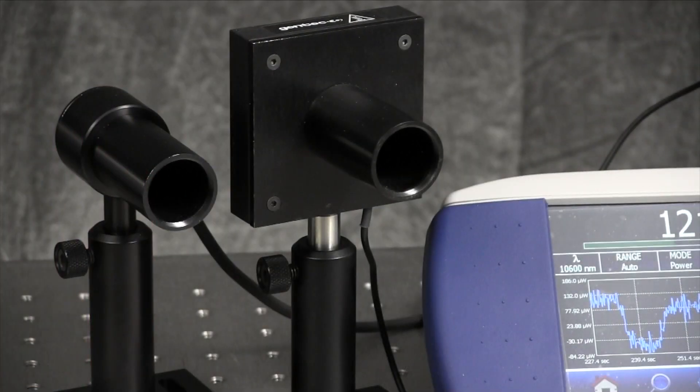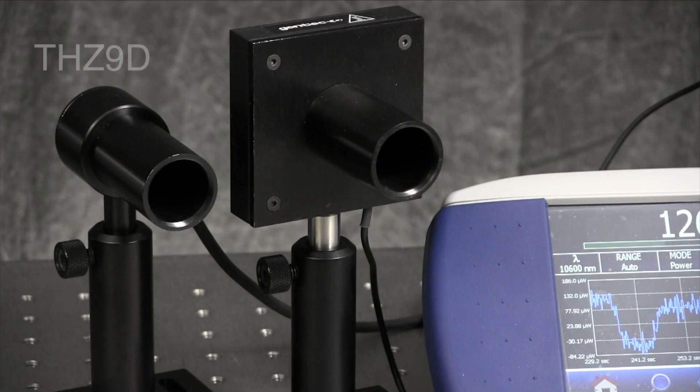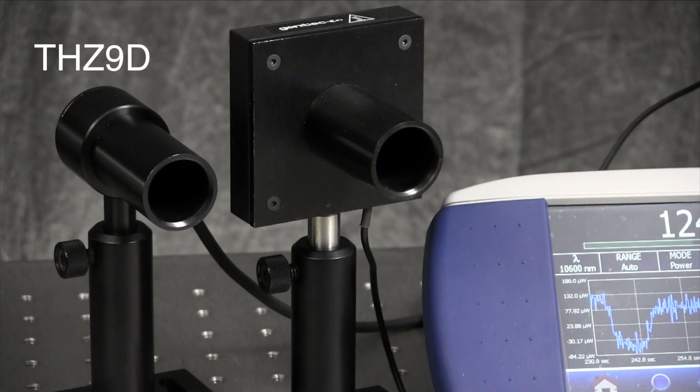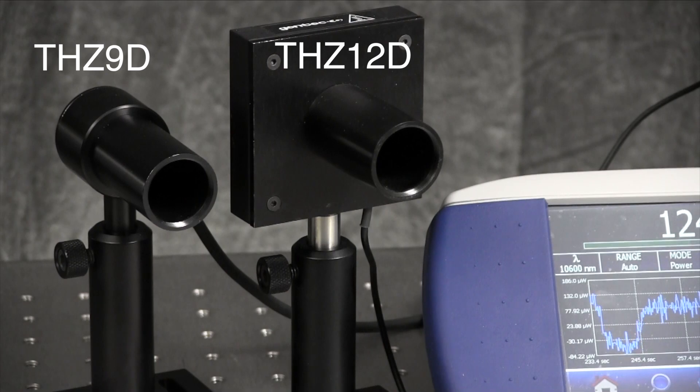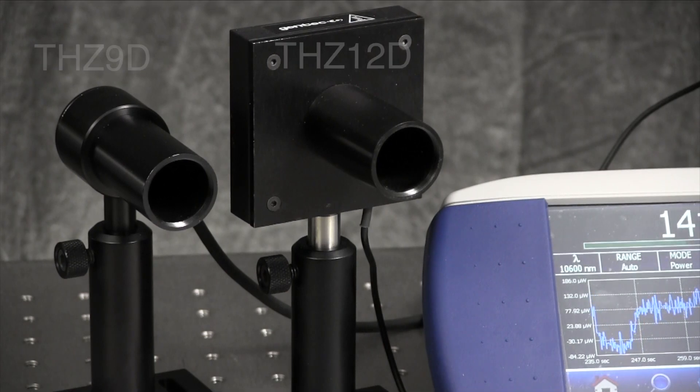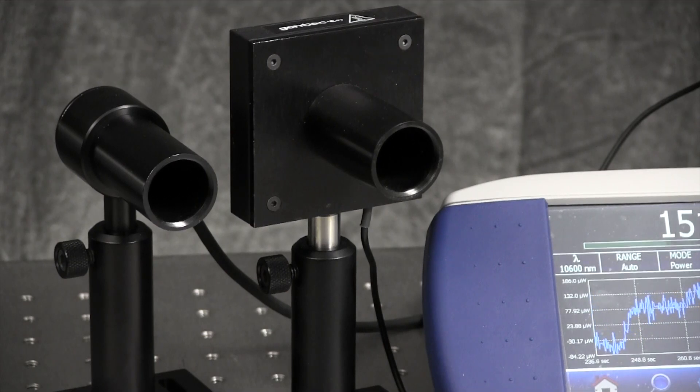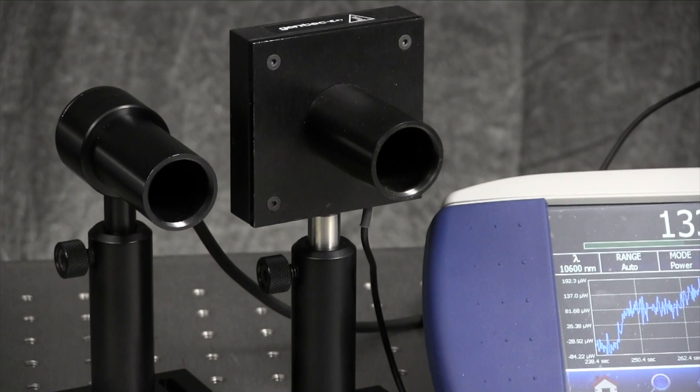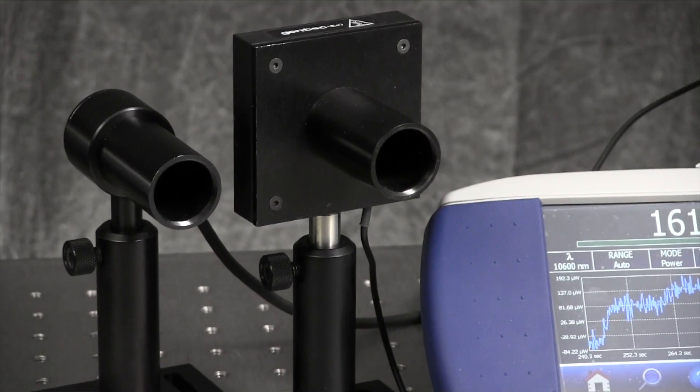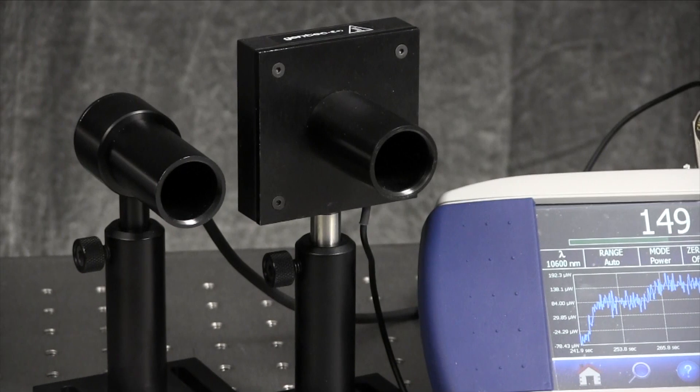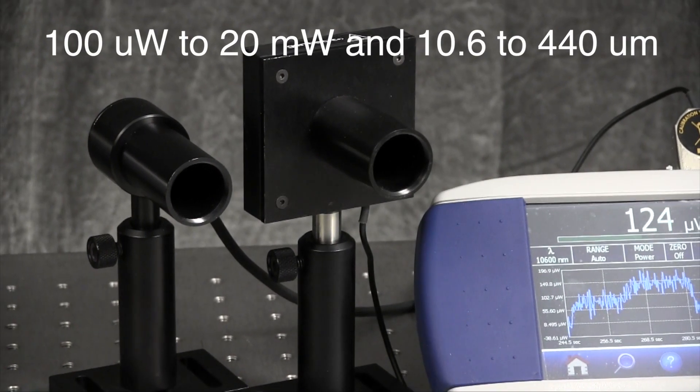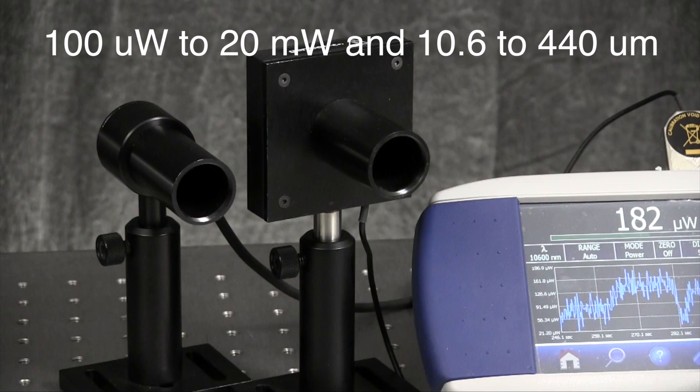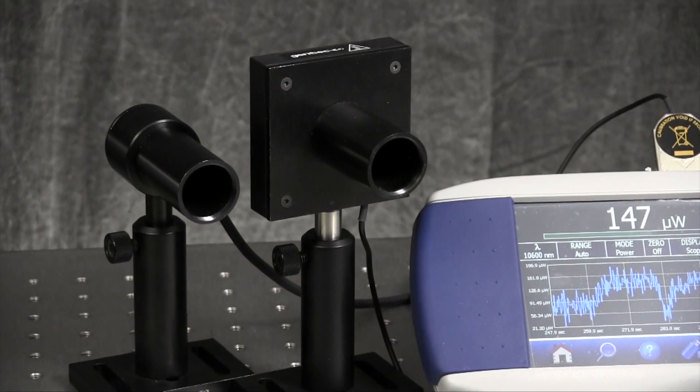We recently created a pyroelectric probe terahertz 9d and a thermopile probe terahertz 12d for use with our Maestro touchscreen instrument as a standalone power meter. The terahertz 9d pyroelectric requires use of an optical chopper running at 10 hertz and can measure from about 100 microwatts to 20 milliwatts and from 10.6 to 440 microns.